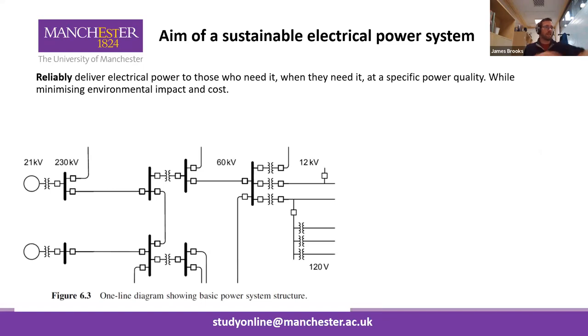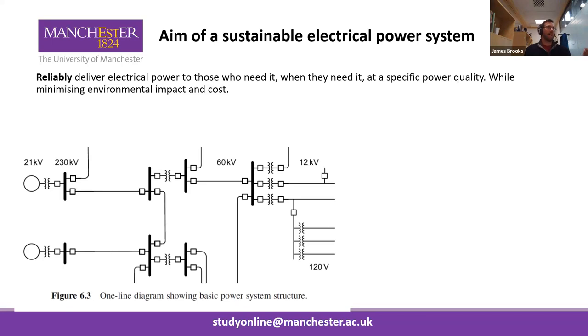Next is reliability. On a large network, individual components experience faults relatively regularly. If we lost a particular line, could we — through all the other connections — keep the network running and provide supply to the households that needed it? We'd expect the system to stay running with the loss of any single component: a transformer, a generator fault, a busbar fault, or a line fault. But it's not that simple, because wind turbines create continual variation in power input, and loads change regularly with people changing demand.